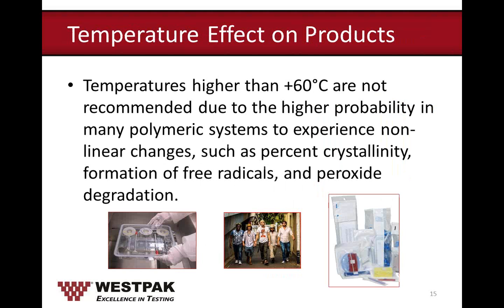According to ASTM F1980, temperatures higher than 60°C are not recommended because of the higher probability that many polymeric systems will experience non-linear changes, such as changes in percent crystallinity, formation of free radicals, and peroxide degradation — affecting materials like pouches and thermoform trays.